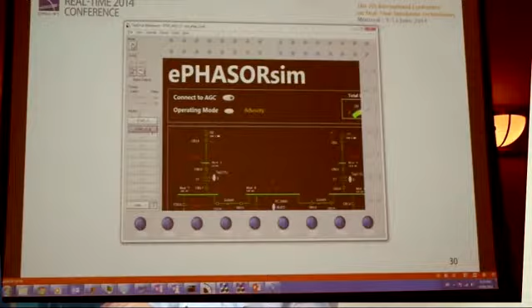But we can have some displays to show the voltage and other controllers, for example change of loads or change of tap position, and we can add other parameters to visualize. Here I have the data I am sending to the AGC system—as shown in the other slide, it's the bus voltages, active and reactive power, and frequency of each synchronous machine.